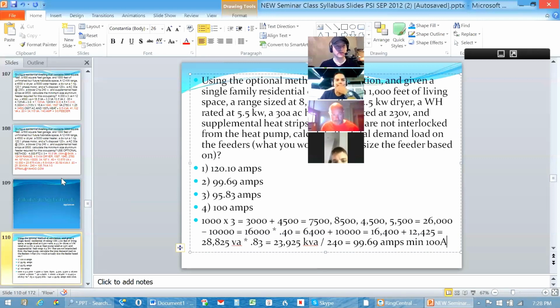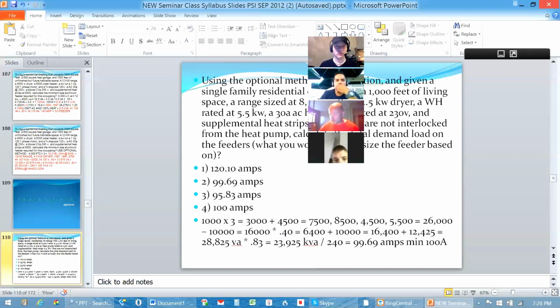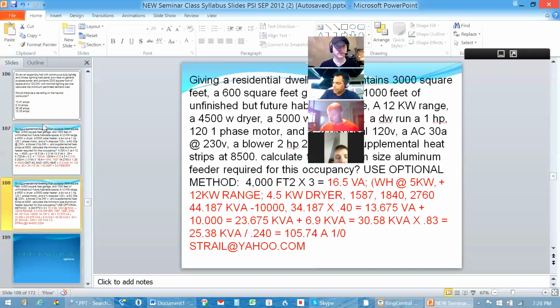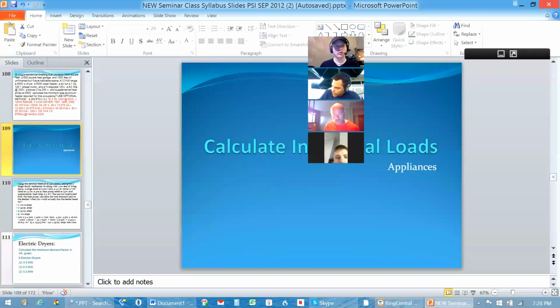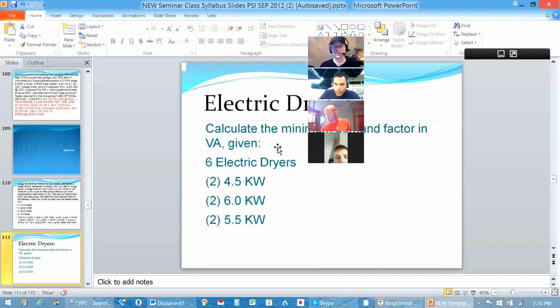Individual loads, when I'm talking about back to the standard method, okay? So we're done with the optional method and we're moving back to the standard method to pick up a couple of things. I'm looking at individual loads for dryers, right? Dryers are going to be one of those things that you have to be careful of. First and foremost, we're looking at pages 70 and 71. At the bottom is 220.54 for the dryers, and the table that's on the left-hand side of page 71.